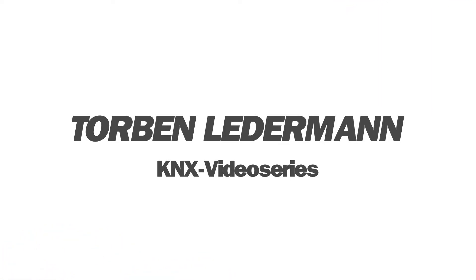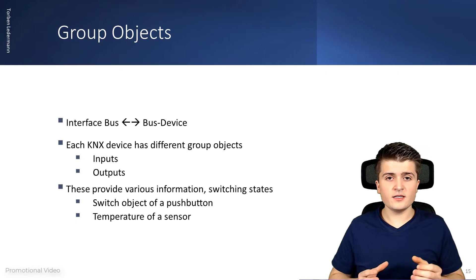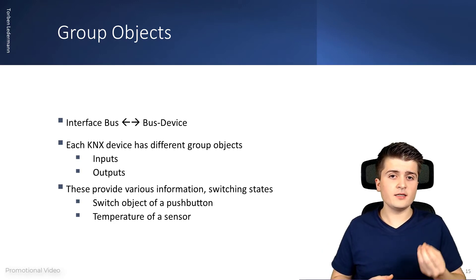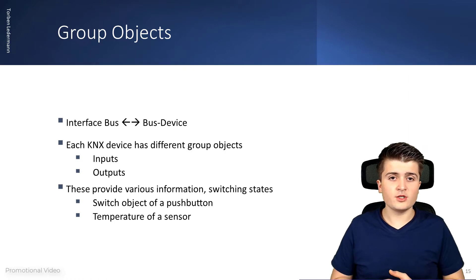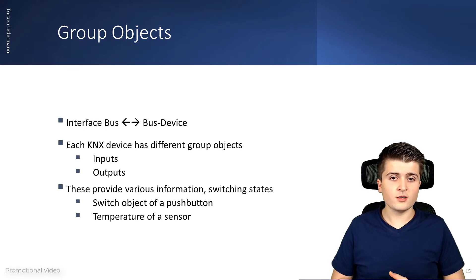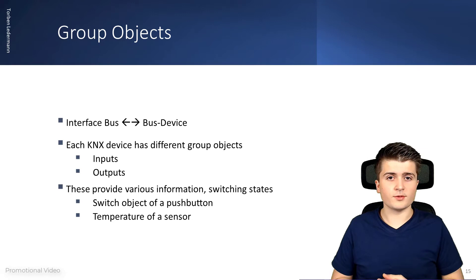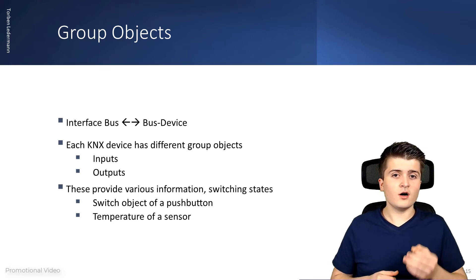How we can achieve this we will see after the intro. Group objects are the interface between the bus and the bus device. All information provided by a KNX device is represented as a group object in the ETS. So this means, for example, in the case of a sensor, the information of pressing the button, the temperature, or the humidity is represented as a group object. And in the case of an actuator, the individual channel functions — such as switching, blind movement, or dimming — are represented as a group object.